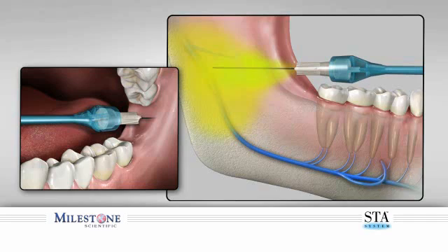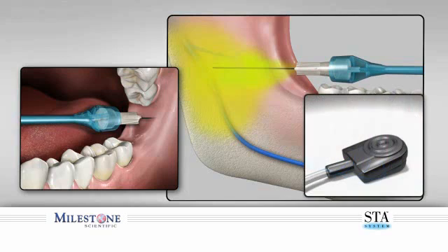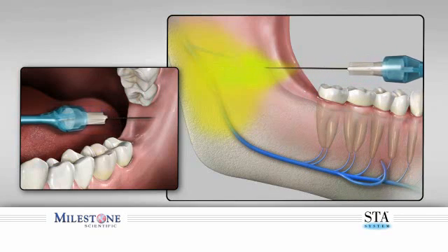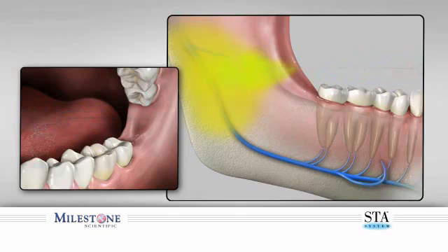To avoid anesthetic solution spray back into the patient's mouth, perform the following: while the needle is still embedded in the patient's tissues, depress and release the foot control pedal. Count three beeps after releasing the foot control, then totally remove the needle from within the patient's mouth. Direct the needle away from the patient, as a small amount of anesthetic solution may still be present.